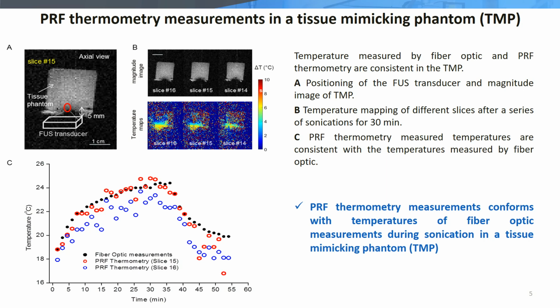For real-time temperature control during a FUS treatment, we established the proton resonance frequency shift thermometry in the Bruker. To start this, we used a tissue mimicking phantom and measured the temperature with fiber optics in parallel to the PRF with the MRI. Our PRF thermometry measurements conform with the temperatures of the fiber optics during the sonication in the phantom.